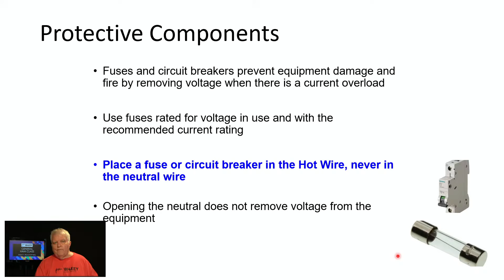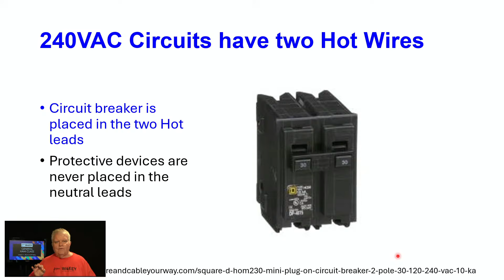The fuse, if it's a 5 amp fuse, should blow with 5 amps. And the fuse should be in the black wire lead or the hot wire lead, never in the neutral wire. The fuse might blow, but that means that still power is inside that piece of equipment. So that's why fuses need to be on the hot side or the black wire. And if you're going to have an amplifier in your ham shack, you probably want to consider having 240 volts in the ham shack. 240 volt circuits have 2 hot wires. And so a circuit breaker is placed in each of the 2 hot leads. Never in the neutral leads.